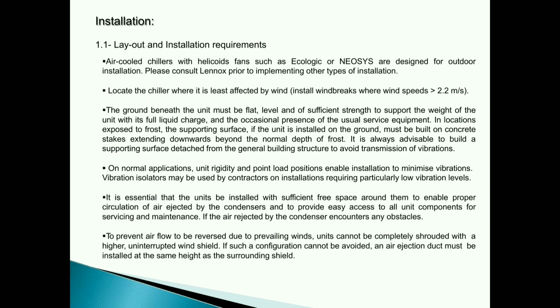In locations exposed to frost, the supporting surface, if the unit is installed on the ground, must be built on concrete stakes extending downwards beyond the normal depth of frost. It is always advisable to build a supporting surface detached from the general building structure to avoid transmission of vibrations. On normal applications, unit rigidity and point load positions enable installation to minimize vibrations. Vibration isolators may be used by contractors on installations requiring particularly low vibration levels.